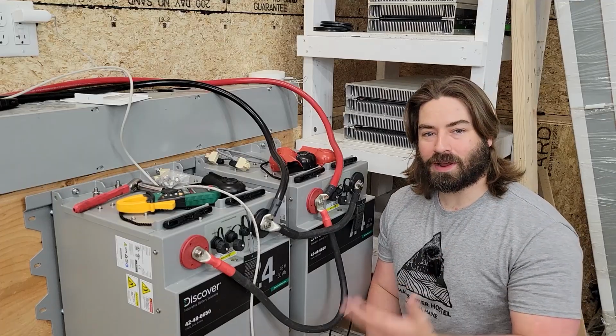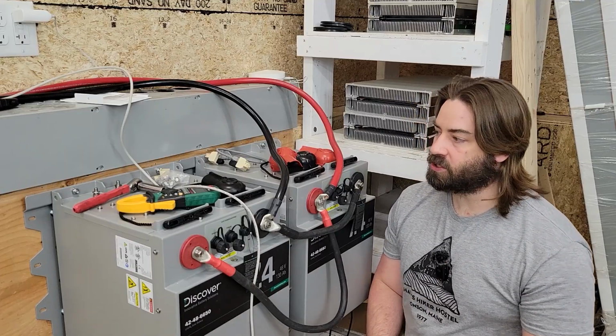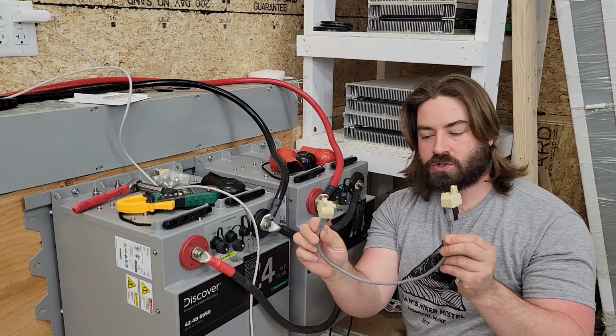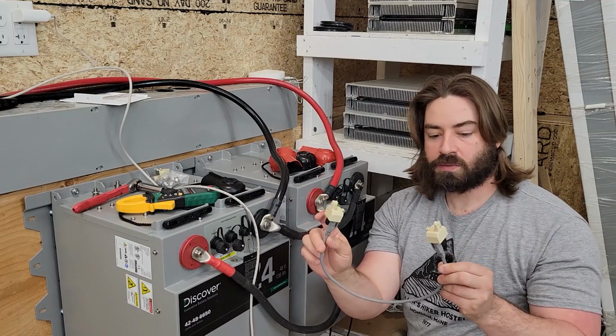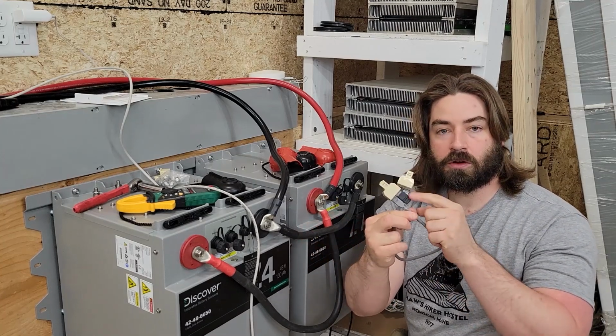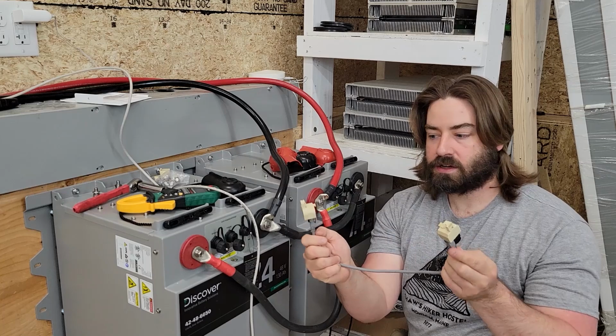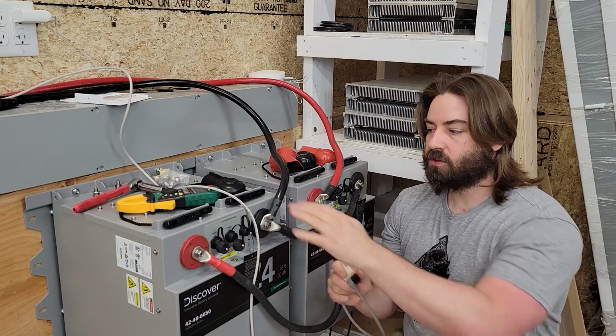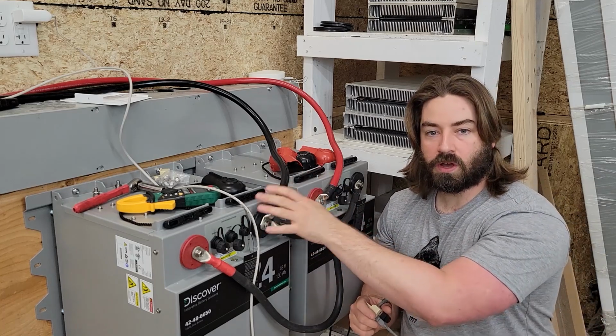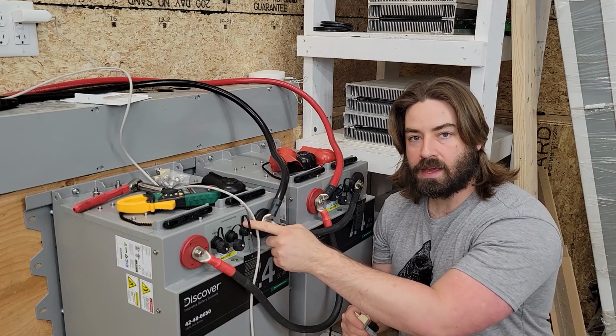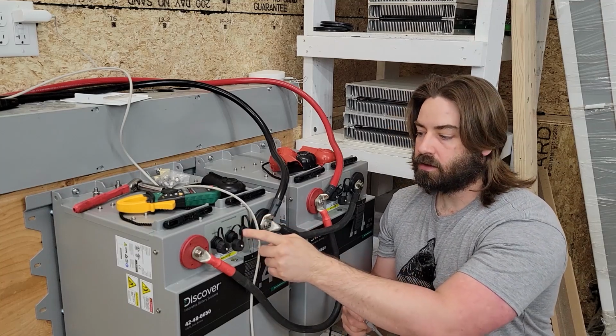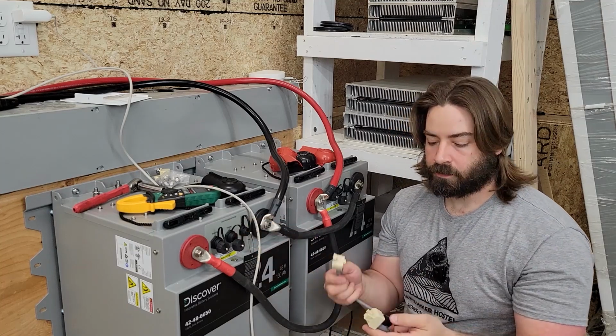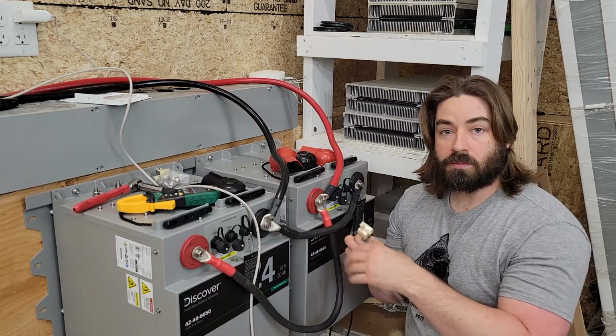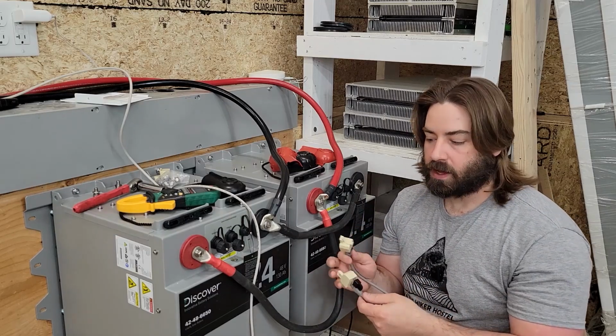At this point, we're ready for the data wires, the communication. This little setup with the short Ethernet jumper and the splitters, and don't forget the terminators on the ends, is going to let me join the 2 batteries together. So the 2 batteries will talk to each other using the AE bus RJ45 port so they'll communicate up as one big battery bank to the Schneider.